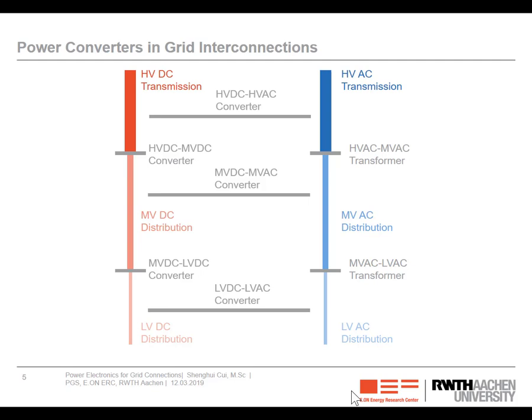Of course, most of us are already familiar with interconnecting HVAC transmission and MVAC distribution. We use 50 Hertz or 60 Hertz line frequency transformers, and for MVAC to LVAC, it's the same. But for DC, from HVDC to MVDC, we need a DC-DC converter to step down the voltage. So we would need an HVDC to MVDC converter, and from MVDC to LVDC, we would need a DC-DC converter as well.